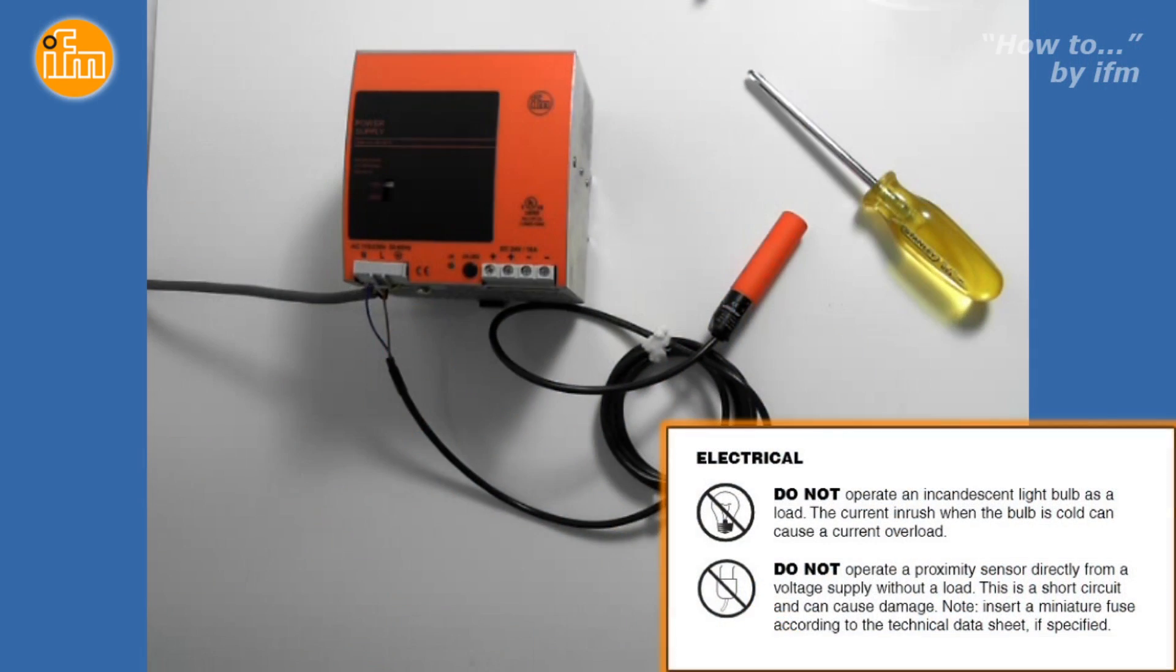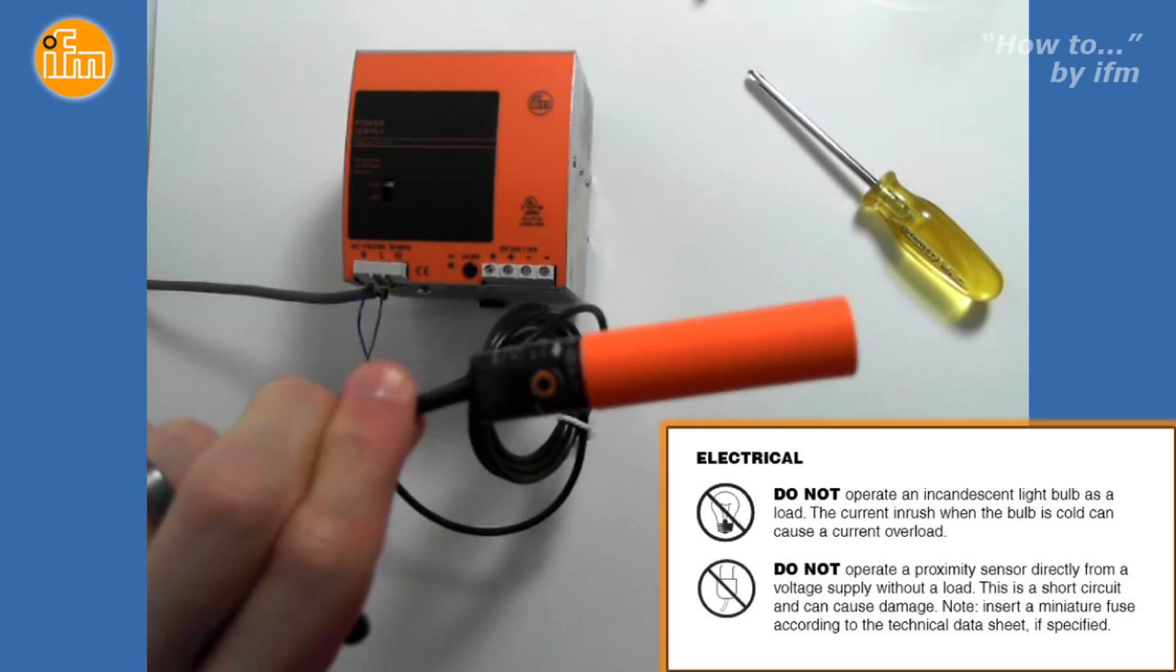As seen here, a sensor connected directly to the power supply without a load is incorrectly wired. When the sensor is tripped, the circuitry in the sensor will overload and the sensor will no longer function.